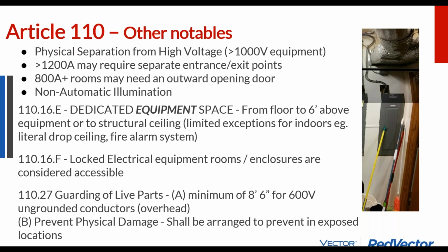Let's see. So dedicated equipment space. If there are exposed parts, like you're building your own battery case, that area needs to be locked so that service personnel only enter it. So that gets into maybe shared spaces not being particularly good. If you're putting your batteries in a service closet that shares it with storage and the water softener and all that, then you might need to put an additional cage around your exposed batteries.